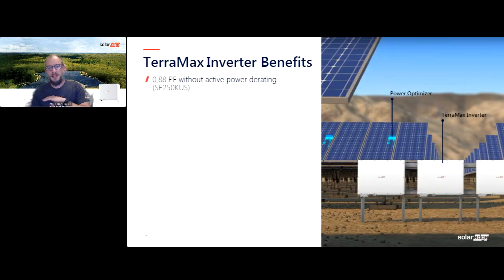So let's start going through the benefits. So I already talked about the 0.88 power factor, and this may seem like, okay, what's the big deal? But the big deal is there's a lot of utilities that are requiring a 0.95 power factor rating for the inverters that are on site. And when you do a 0.95 or a 0.9 or even a 0.88, as you could go with our inverters, you're limiting the amount of active power that inverter can produce. Typically, an inverter is rated for, let's say, 250 kilowatts or 250 kVA of apparent power. When I operate at a 0.95 power factor, I'm now derating my active power in order to produce reactive power in conjunction with my active power.